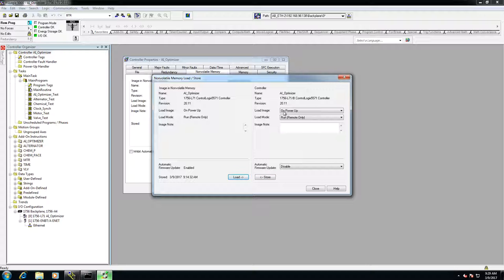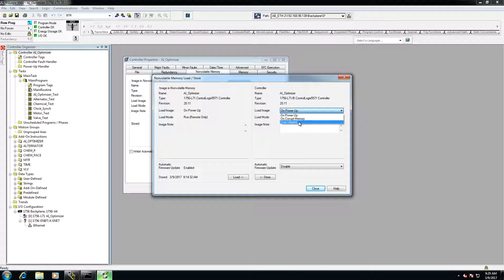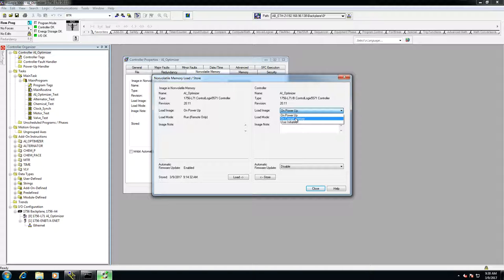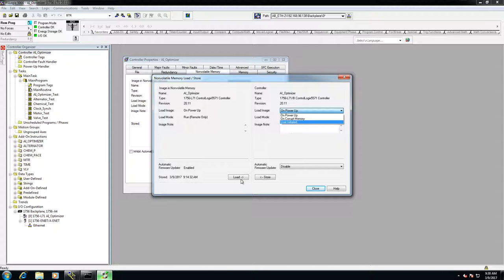You'll have the load image option, and that's when to actually load it. On power up means every time it powers up, if it finds that the program is not on there, it will actually load it in. On corrupt memory, if it sees that there is no program or it's in fault, it can reload it. And then user initiated would be you would have to actually come into the program and click the load button.